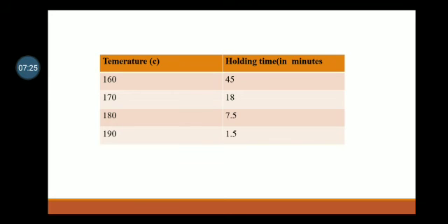Temperature and holding time in minutes. Temperature is 160 degrees Celsius, holding time is 45 minutes. Temperature is 170 degrees Celsius, holding time is 18 minutes. Temperature is 180 degrees Celsius, holding time is 7.5 minutes. Temperature is 190 degrees Celsius, holding time is 1.5 minutes.